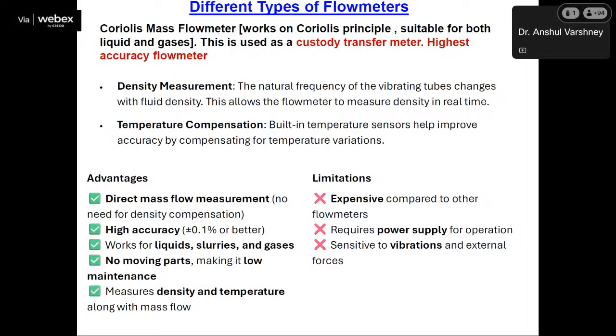So basically, with the help of these Coriolis mass flow meters, you can easily measure the density, and they provide built-in temperature sensors for temperature compensation. These are the highest accuracy mass flow meters, as I said earlier. The advantage of these mass flow meters is direct mass flow measurement, and there is no need for density compensation. The accuracy is pretty good, in the range of 0.05%, and it works well for liquids, slurries, and gas.